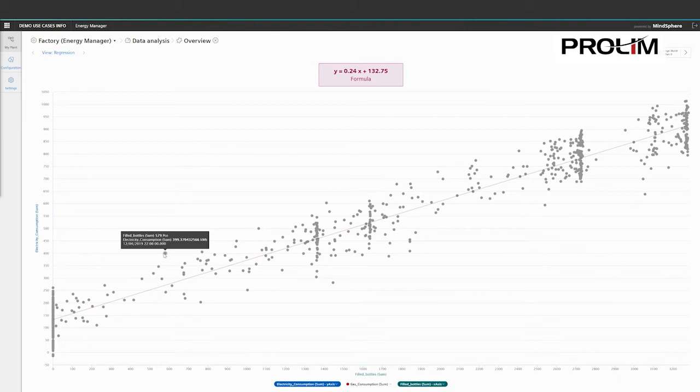The production engineer observes that the dots are scattered with a plus/minus 20% along the estimated consumption depicted by the regression line. This is more than he expects. There is a significant variance of energy required to produce a certain number of bottles. He concludes that there is opportunity to stabilize the process and reduce the amount of energy consumed.